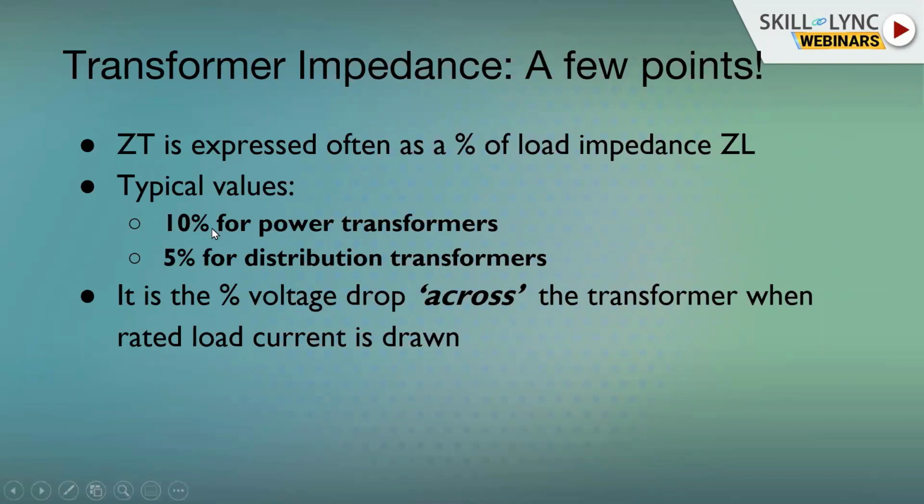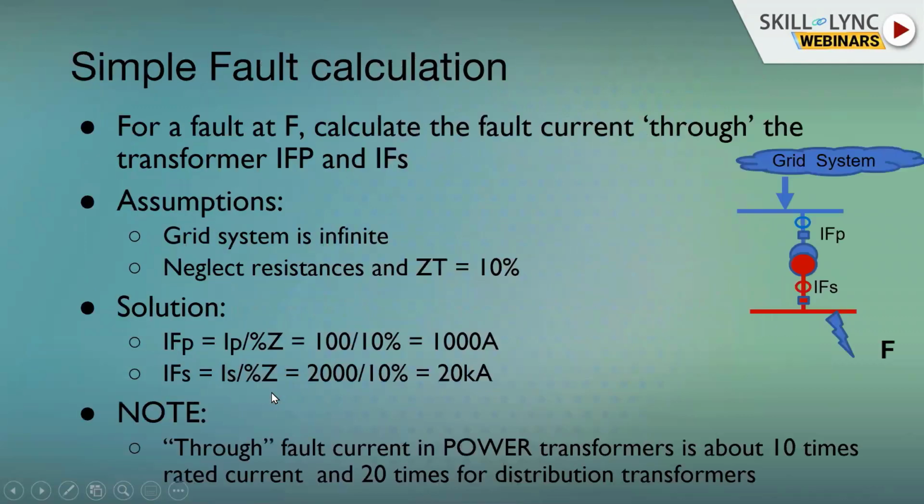And so we keep it a little high and we compensate for this higher value by what we call the tap changers on the transformer. So the higher the impedance, typically the tap ranges are also proportionately higher to compensate for the voltage changes. So we in a way compensate for that. So there's no major issue in the real power system.